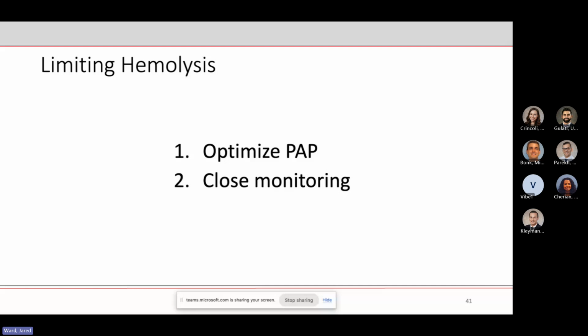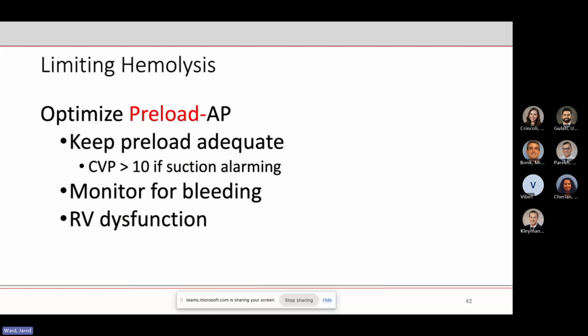So by optimize the PAP, what I mean is you've got to optimize your preload. Not all of these need to have a stupid high preload. You don't have to target a CVP of greater than 10. If the thing is flowing just fine on P8 or P7 and your CVP is 6 or 7, then don't touch it. If you start getting suction alarms and your CVP is low, you should target a higher CVP, because these are preload dependent and afterload sensitive, right? So if everything is going fine, and then all of a sudden you see your CVP go down, be worried about a bleeding event.